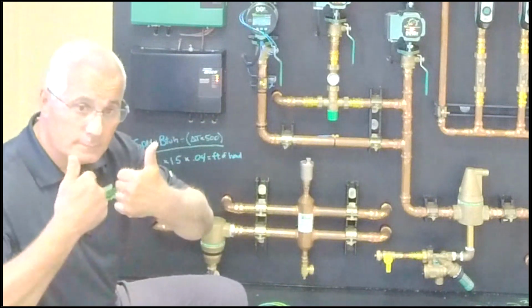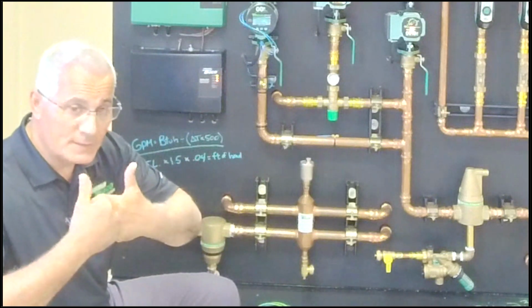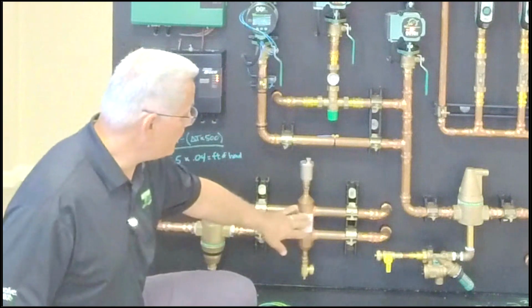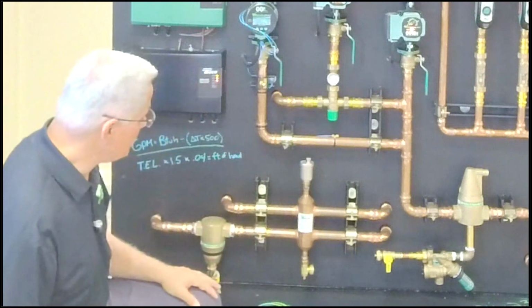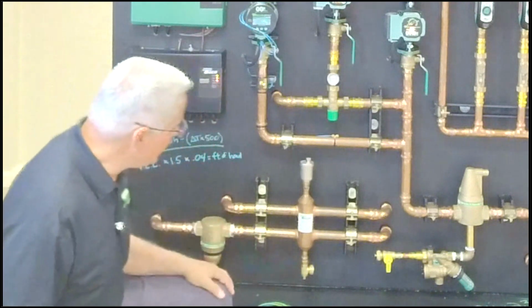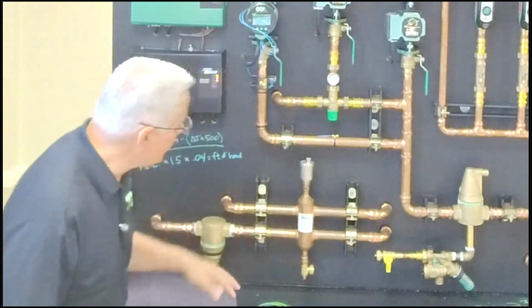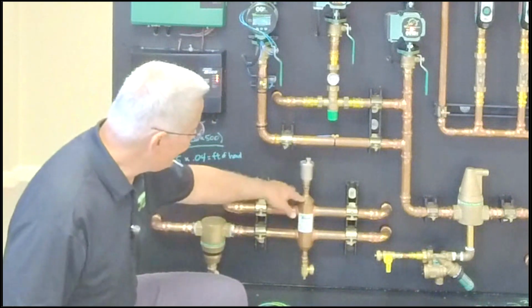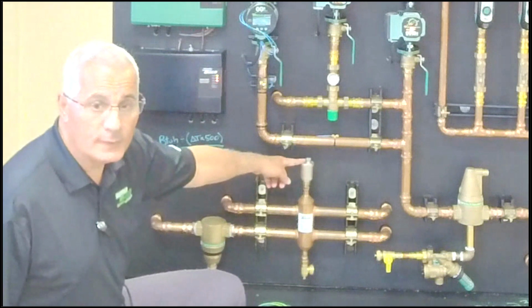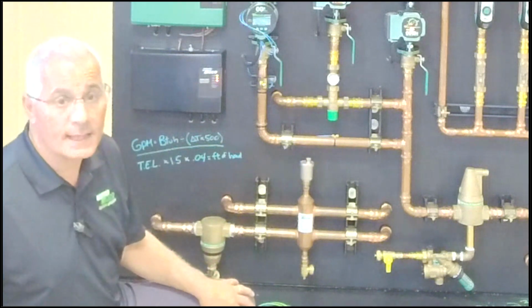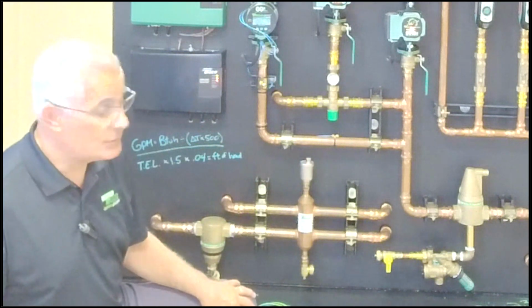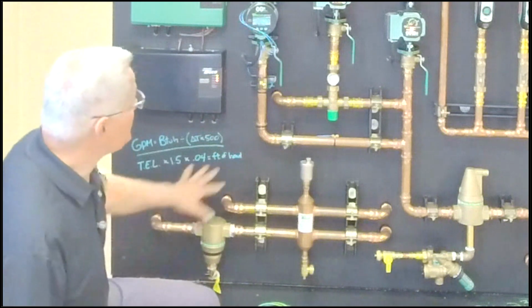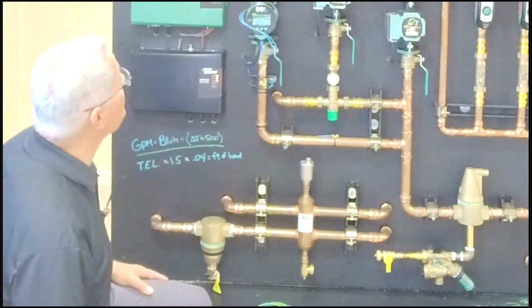So you can either build your closely spaced T's, not a big deal, or you can buy this, and Taco makes this low loss header. I got a valve on the bottom, so I can flush this out if I need to. And since I can capture some air, we can put a 400 series air vent on the top and help capture some air too. All right, so that is on the condensing side of things.